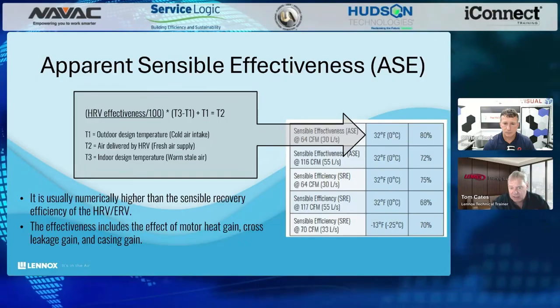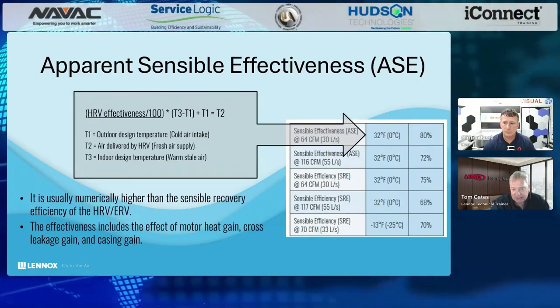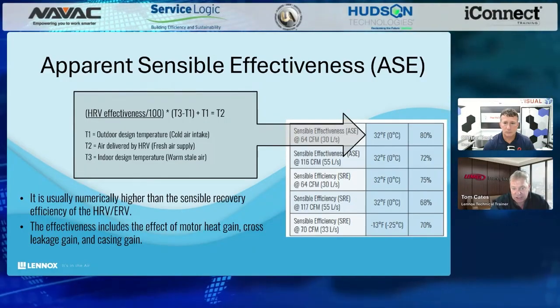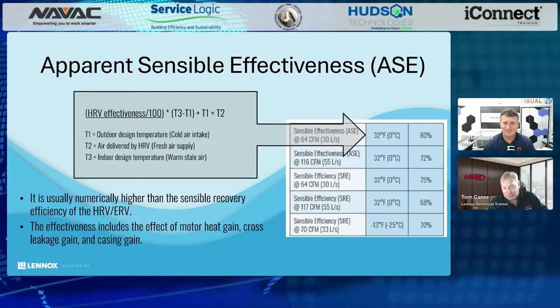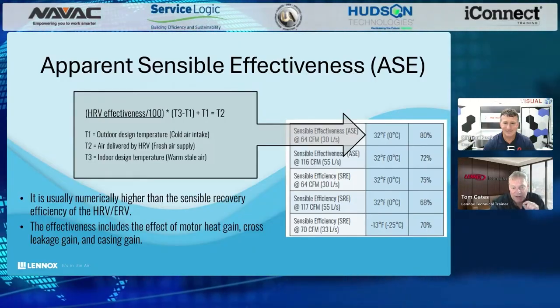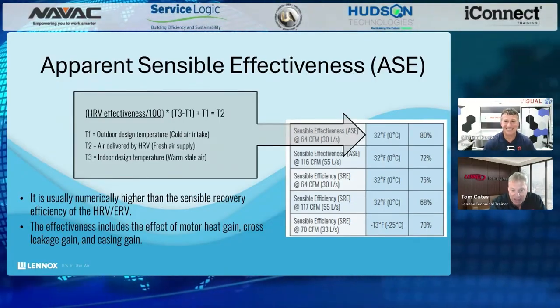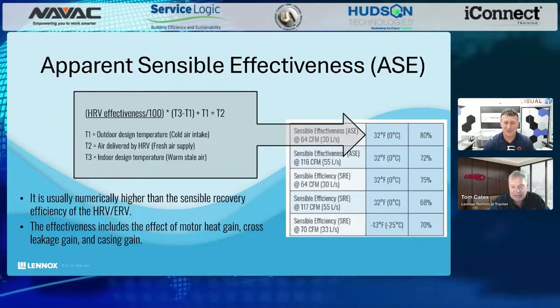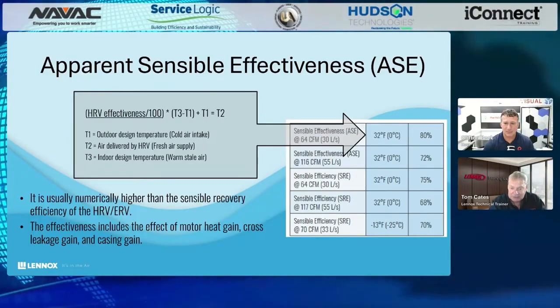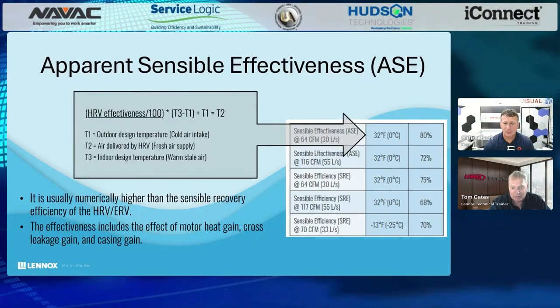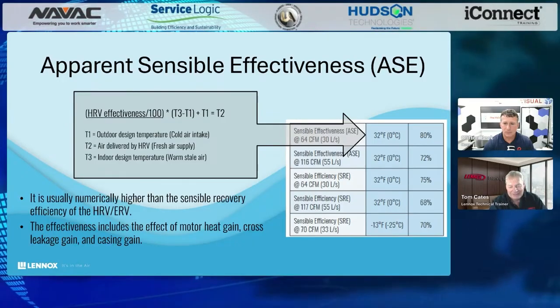If that air enters out of that supply grill at a temperature that's too cold, people are just going to shut it off, or they're going to stuff it full of insulation. So we have to be able to, through a math calculation, determine what that delivered air temperature is, so that people aren't affected to a point where they want to shut it off.